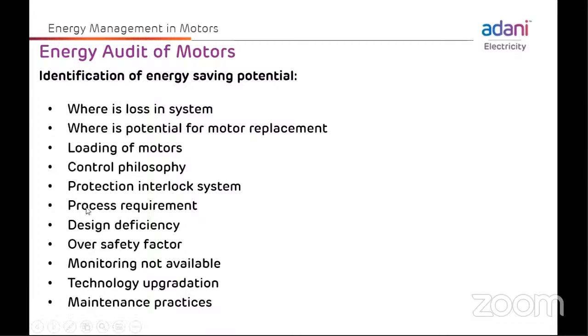Then process requirement - here one point is, what is the process requirement, is also important. We should identify the process requirement. Suppose there is a flow requirement of 250 ton per hour for an equipment system, and our equipment is giving 330 ton per hour. Then there is scope of improvement - you can reduce the speed. That way you can identify the process requirement, because we are not changing the process, we are using the same process. So for meeting the process criteria, what are the chances or losses in the system, we should identify that.